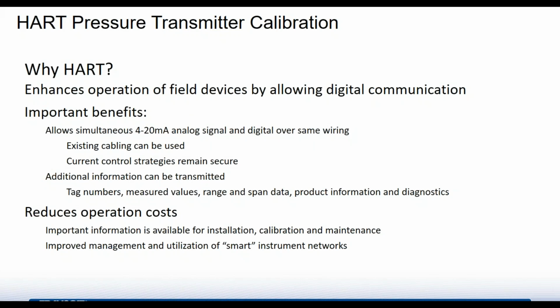So let's look at some of the reasons why HART is used. First off, it allows you to simultaneously do your 4-20 milliamp measurements and talk digitally with HART across the same wiring. So you don't have to change the wires that you're using, use the same cabling, makes all that information easy to get at. You can also not just do calibrations, but you can also check out the tag ID numbers, your measured values, ranges, and of course, all kinds of commissioning information required for a transmitter. So all this helps reduce operation costs and makes life a lot easier having those smart instruments out there.